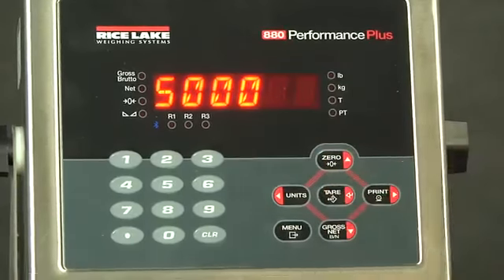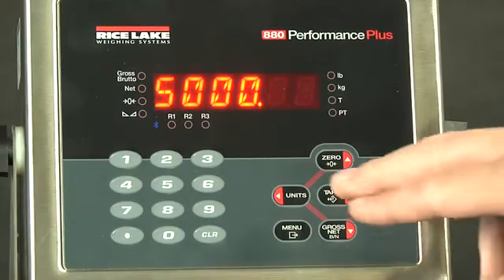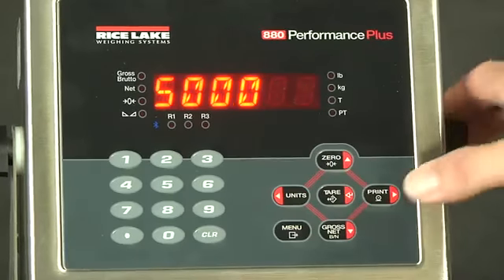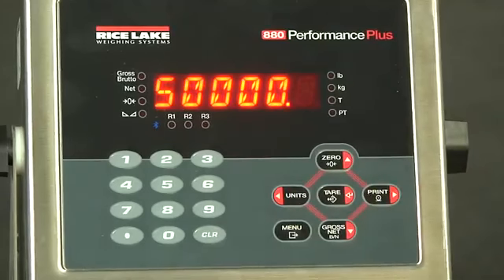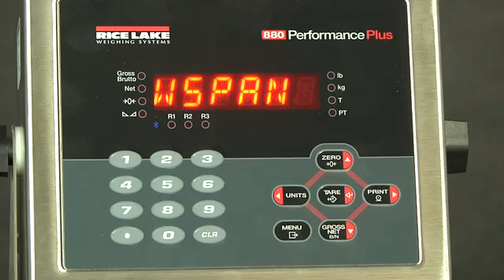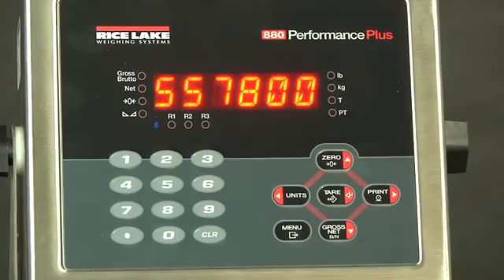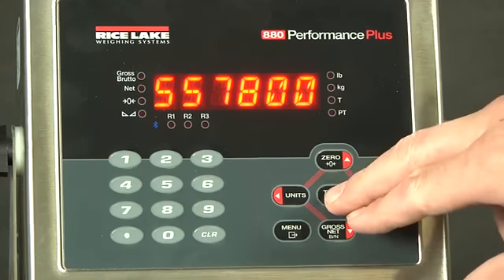After you hit enter the first time, it then allows you to choose a decimal point location. So if you're going to 500, you could move it like that, or even 50,000. That is available. However, for this demonstration, we are only calibrating to 5,000. We will now hit enter, and it moves us to our W span. At this point, you would put all weights that you are using onto the scale in order to calibrate the span point. The span point needs to be at least 10% of the scale's capacity, but it's often recommended to use as much as possible. We will now add the weight to our scale, press enter. Again, this is our current span counts, so in order to determine our new counts, we must press enter.